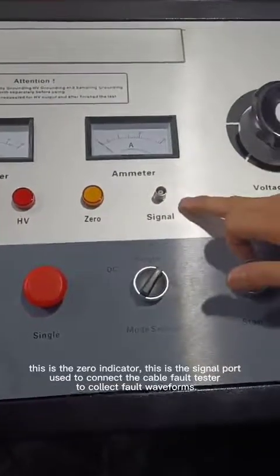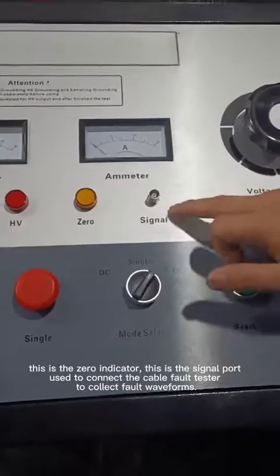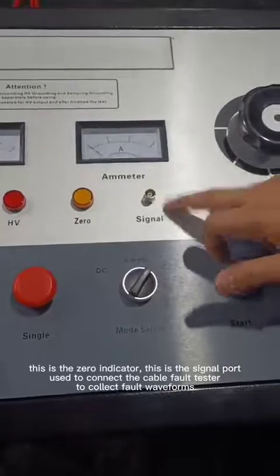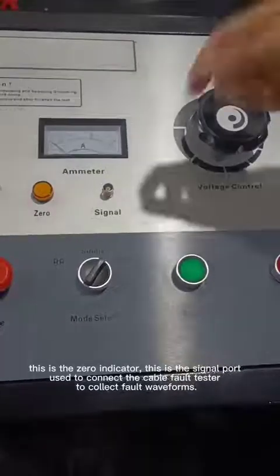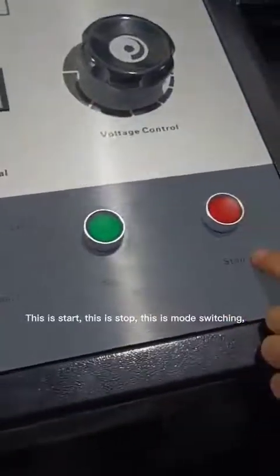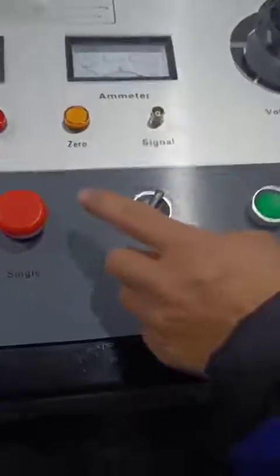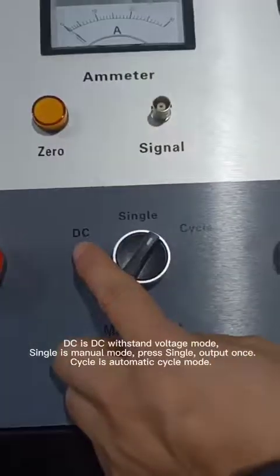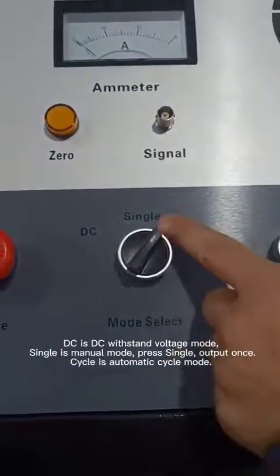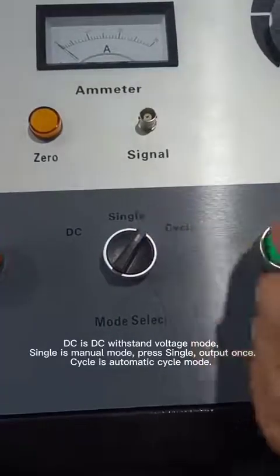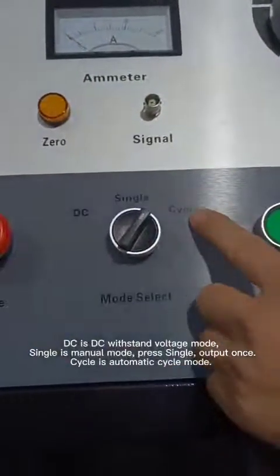This is the signal port used to connect the cable fault tester to collect fault waveforms. This is start. This is stop. This is mode switching. DC is DC withstand voltage mode. Single is manual mode. Press single, output once. Cycle is automatic cycle mode.